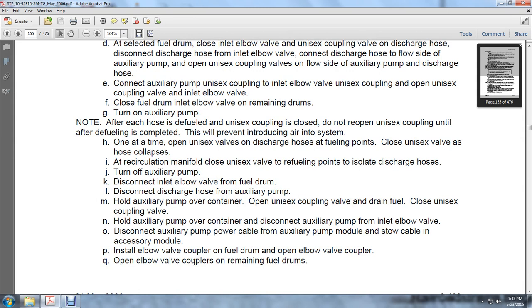At the recirculation manifold, close the unisex valve of the refueling points to isolate the discharge hoses. Turn off the auxiliary pump. Disconnect the inlet elbow valve from the fuel drum. Disconnect the discharge hose from the auxiliary pump. Hold the auxiliary pump over the container. Open the unisex coupling valve to drain fuel.